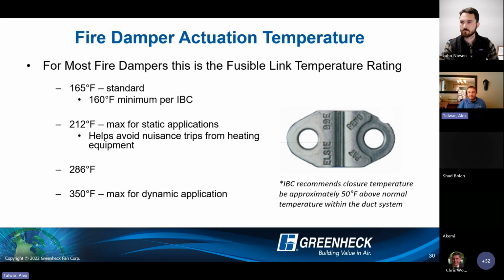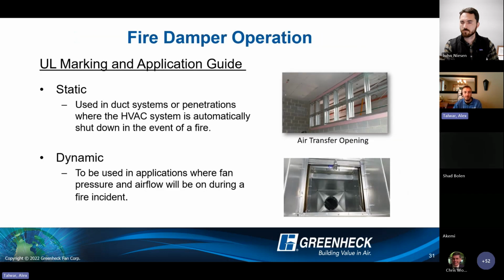Standard ambient air, if you're not heating or you're not living in too warm of a climate, 165 is the minimum standard link and usually okay for a majority of applications. But again, if you are dealing with heated air, you might want to bump that up a little bit. Talked about this one already in terms of static versus dynamic, right? So typical static dampers at an air transfer opening, it's not going to be seeing a significant amount of velocity going through there or have to withstand a ton of pressure. Or if we're tied into a system that automatically shuts down in the event of a fire, that damper won't need to close against any velocity or pressure. So a static rated fire damper is needed in those cases.